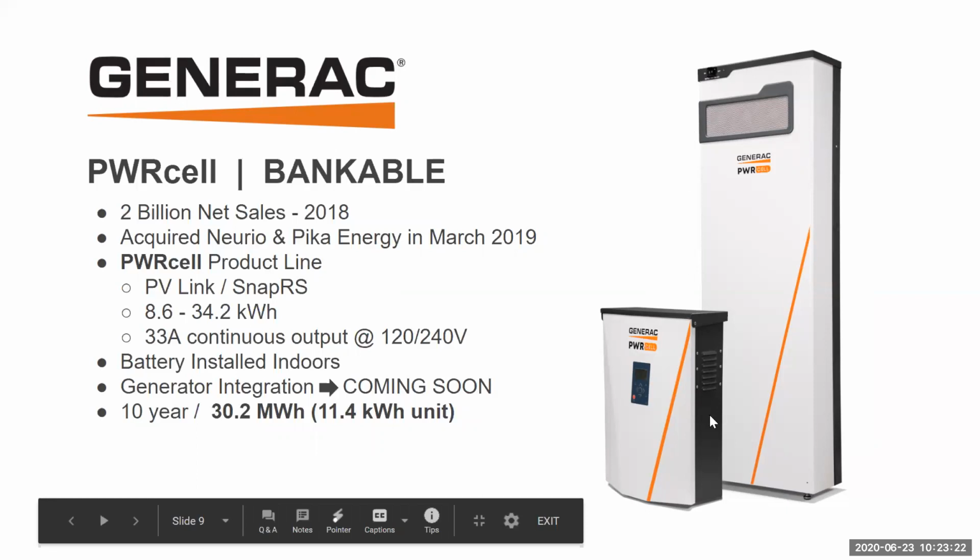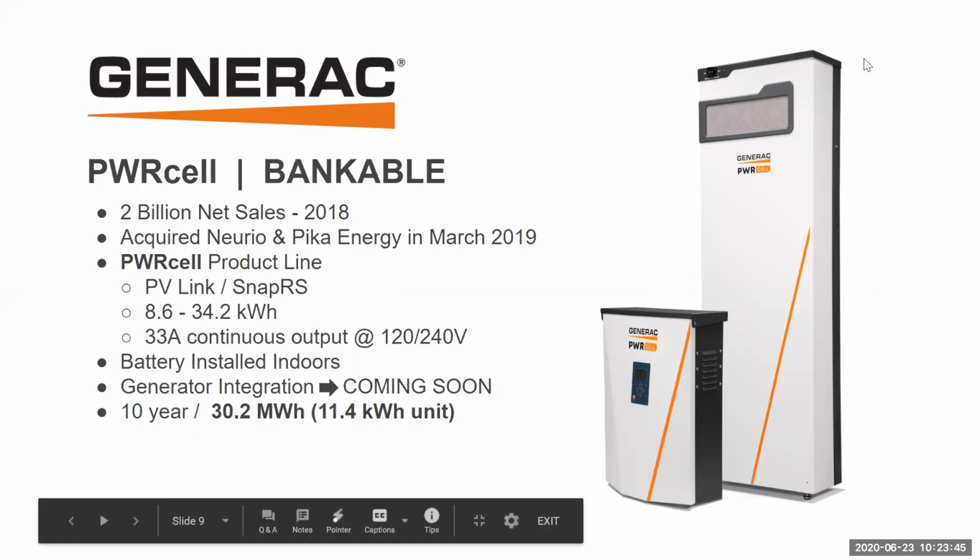And this can hold between 3 and 6 battery units. So that means that we're going to be getting between 8.6 and 17.1 kilowatt hours of storage per enclosure. But we can do 2 enclosures on a single inverter. So if we wanted 34 kilowatt hours, we would have 1 of these inverters and 2 of these cabinets with 12 of the batteries filling those cabinets. So Generac is a DC coupled solution, which means that you just need the modules and these 2 components.